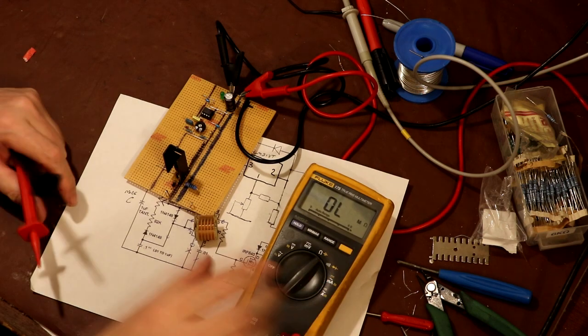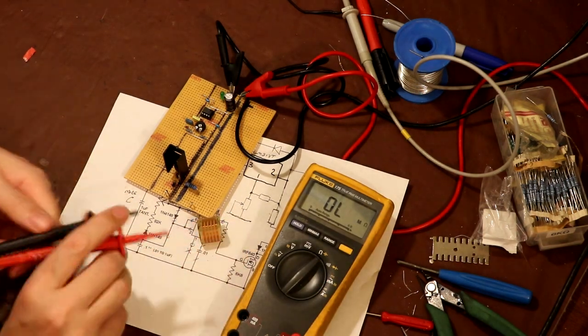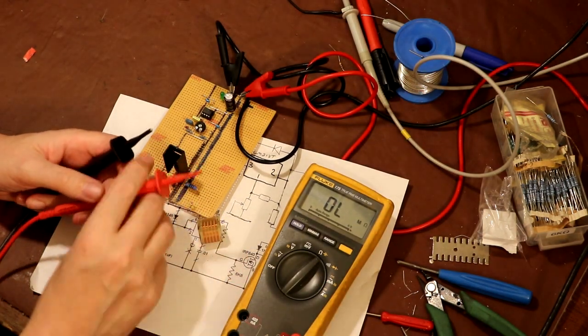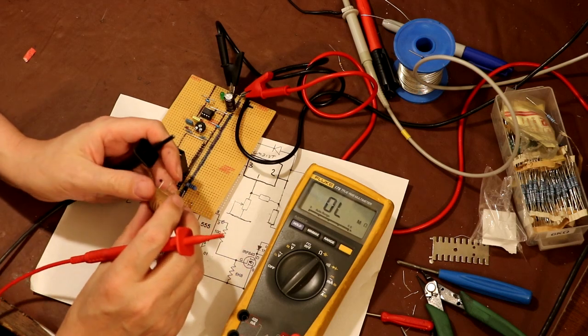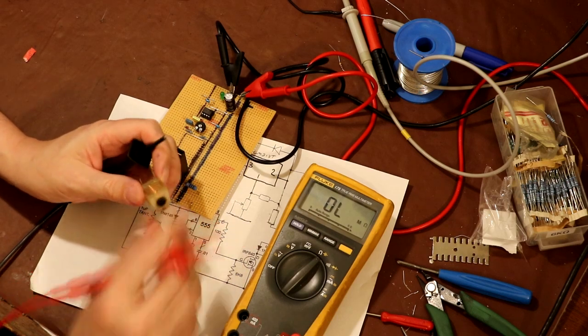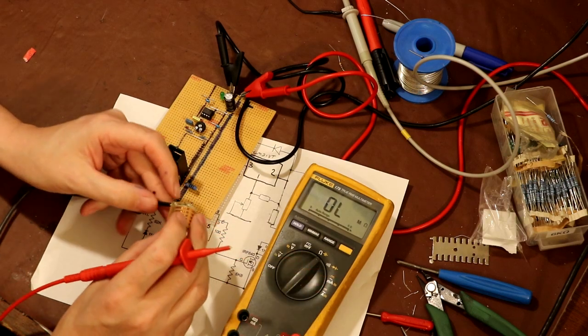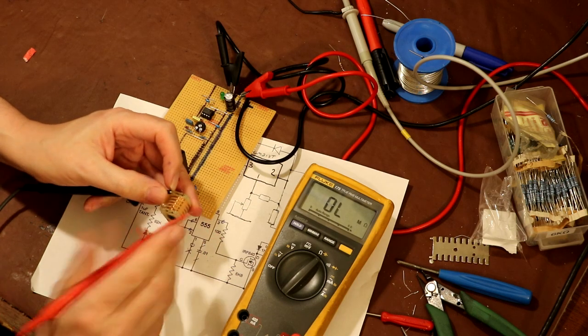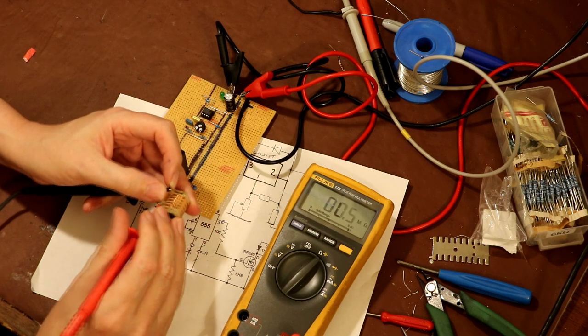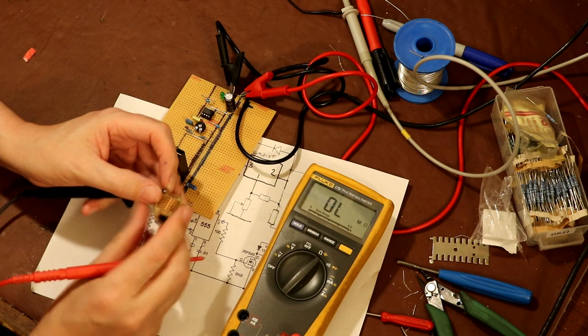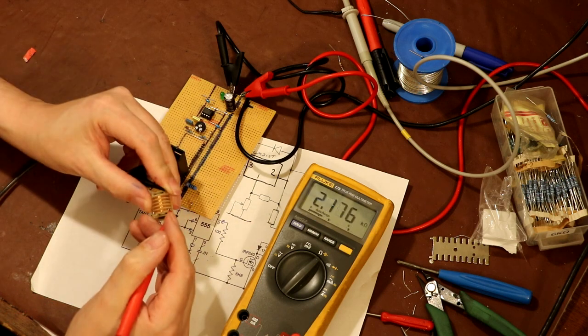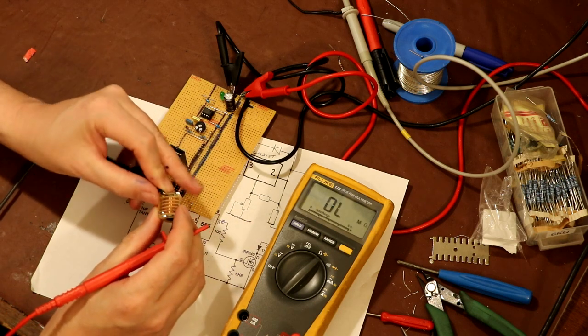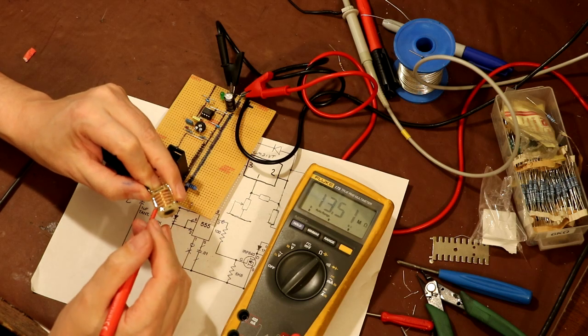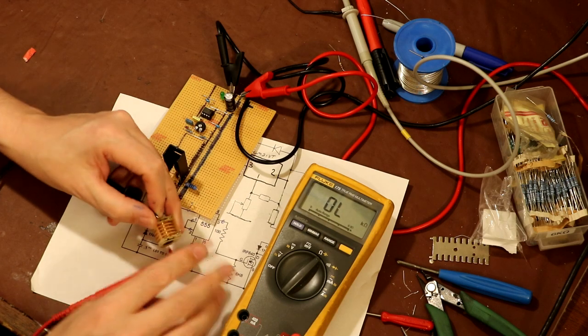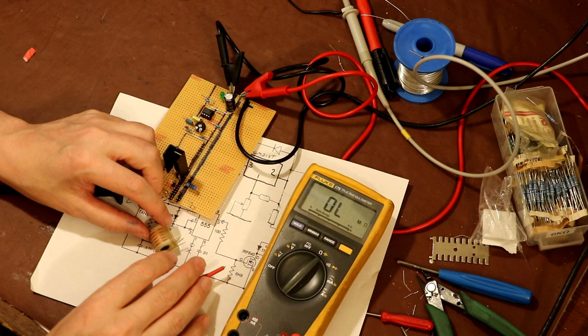That should be quite easy to do, because the secondary winding is going to have many thousands of very fine turns of wire, so that's going to be the high resistance side, and the primary side of the winding is going to be low resistance. So let's just see what that is. Okay, so that's 0.5 ohms. Let's check the other side — 2 kilo ohms. So I'm fairly sure the 0.5 ohm side is going to be our primary.